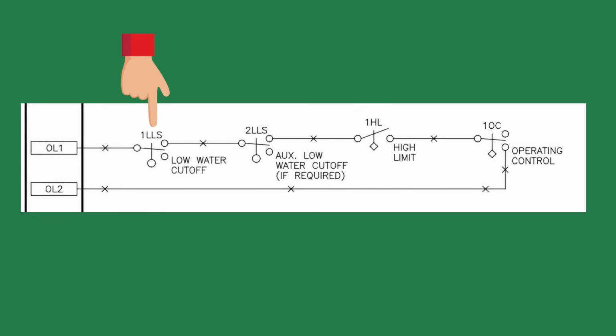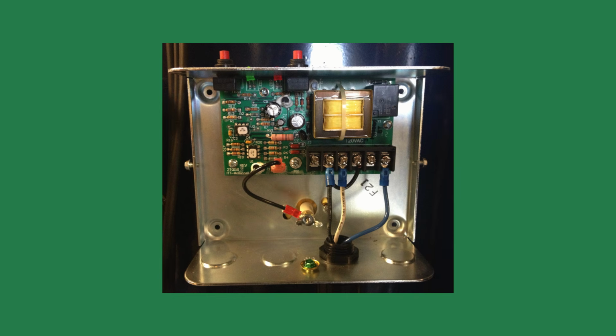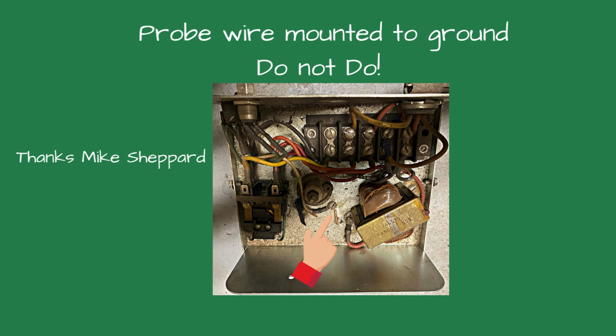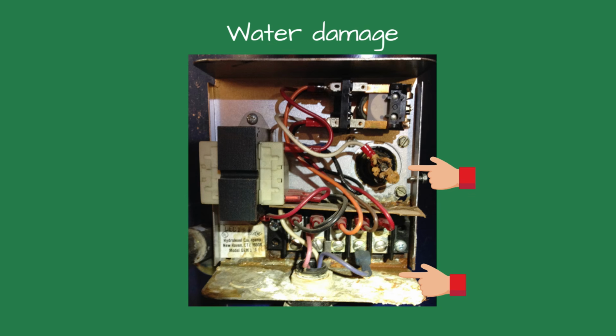Another thing to be careful of is where you wire the new low water cutoff into the safety circuit. Some manufacturers want the low water cutoff wired in first before the other controls. When maintaining the control, the first thing I do is shut off the power. Then I remove the cover, double checking that the power is off. I verify all the wiring connections are snug and make sure the probe and control are properly grounded. Excess pipe dope or Teflon tape can interfere with the conductivity, so keep that in mind. Look for loose wires or evidence of water damage. It could have leaked from a pipe above or backfed through the probe. If you see moisture in the control, replace it.